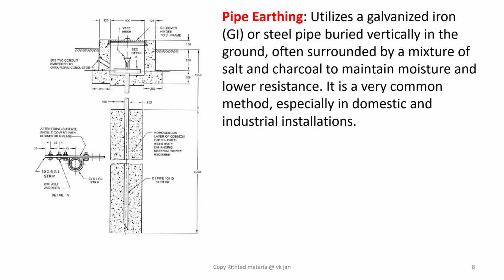Friends, we are discussing pipe type earthing which is recommended by CPWD also. In this there are two different portions. One is very near to the ground, through which an earthing pit is made for watering purposes. We have to keep on putting water during summer periods and other such period. We have to keep this system wet. The second portion implies a rod, a pipe which is perforated and surrounded with such materials which are needed for making this fully conductive.